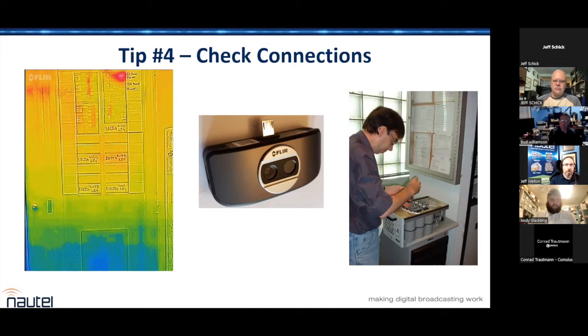Remember that all the rules about emissivity and thermal reflections apply. So if you take a picture of a shiny object, you're not going to get an accurate reading. But if you have a site and you put a little tape X on the floor, and you walk in and take a picture of your breaker panels with that camera from the same point every time, you've got a reference. Next time you look in, you can see if anything changed.